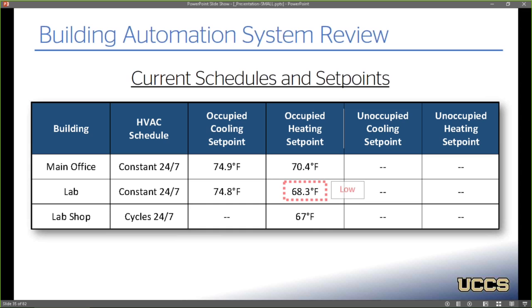The lab heating set point is a little low, but that's only going to save energy in the end, but it could lead to some comfort complaints. And the lab shop set point is a bit high. Considering a shop is typically less insulated than a typical commercial building, and they have these large roll-up doors, maintaining it at 67 degrees all the time, especially overnight when it can get extremely cold, can waste a bunch of energy.